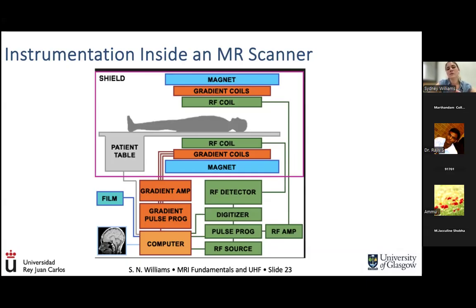It needs to be as close to the person as possible because, if you remember, the main magnetic field itself creates a very strong signal of the spins all within the longitudinal direction, and the precession of those spins when they're knocked off perpendicularly is a lot weaker. So we've got to get the radio frequency coil close to the subject. That's why it's on the inner layer.